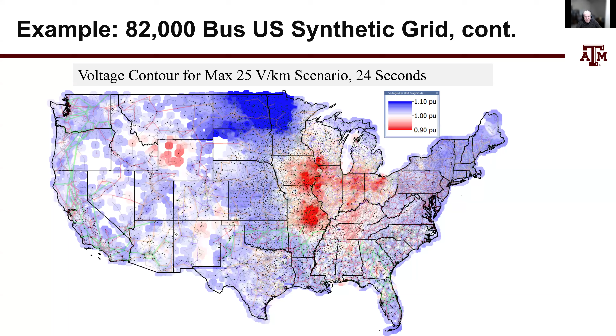One approach is to back down the waveform. I tried it with 50, there was no solution. I backed it down to 25, there was a solution. So I could have iterated and come up with a value, in that case, maybe 35, 40 volts per kilometer, and say, this is the maximum I can solve.